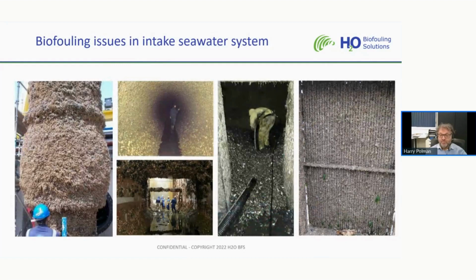Biofouling: besides seawater, biofouling organisms enter the system. And these are some interesting pictures I'd like to share to give you some insight on the impact of biofouling in a seawater intake system. The picture on the left, I like a lot. It's actually a seawater pump, completely covered by a large amount of marine fouling organisms. The picture you see shows the attachment and fouling that occurred from a clean pump to this situation within 1 year. So biofouling can attach and grow in a very fast way in a seawater system.